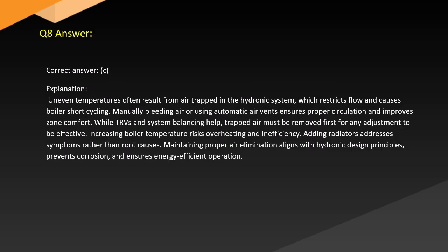Answer. Correct answer: C. Explanation. Uneven temperatures often result from air trapped in the hydronic system, which restricts flow and causes boiler short cycling. Manually bleeding air or using automatic air vents ensures proper circulation and improves zone comfort. While TRVs and system balancing help, trapped air must be removed first for any adjustment to be effective.